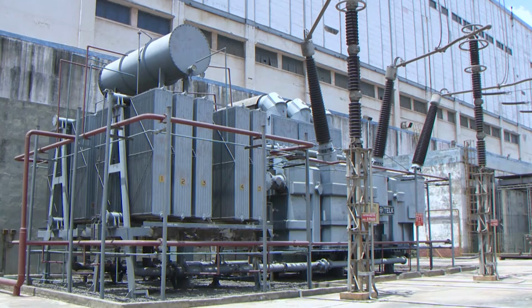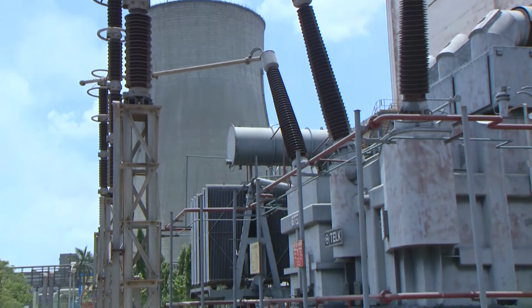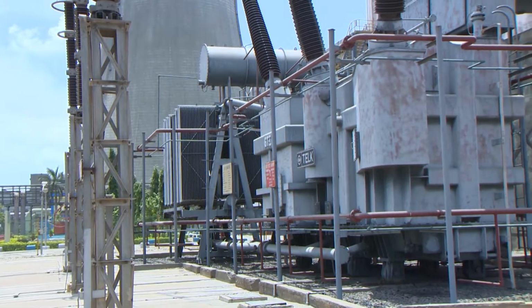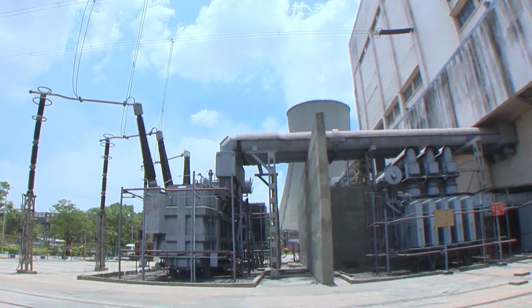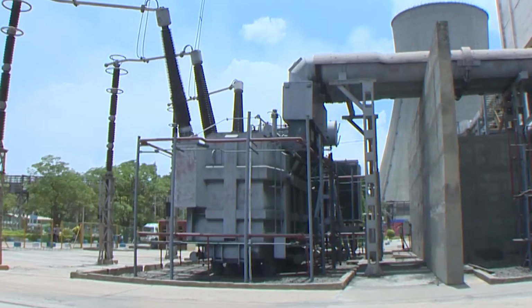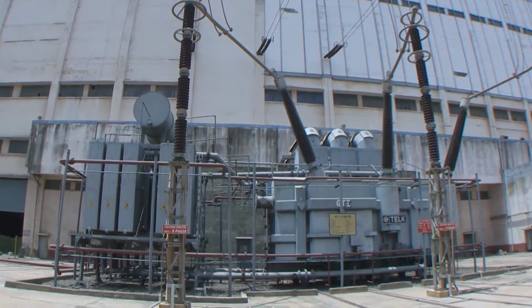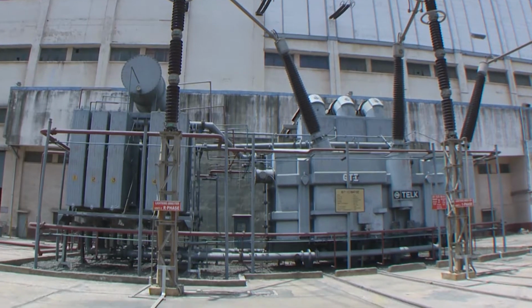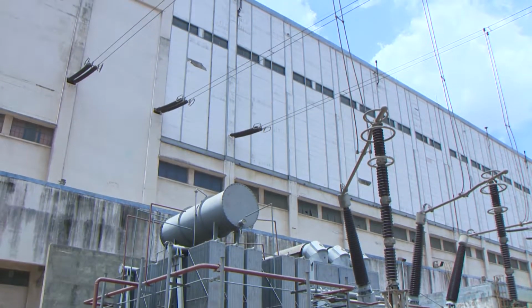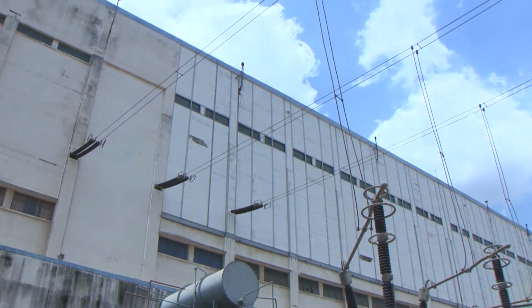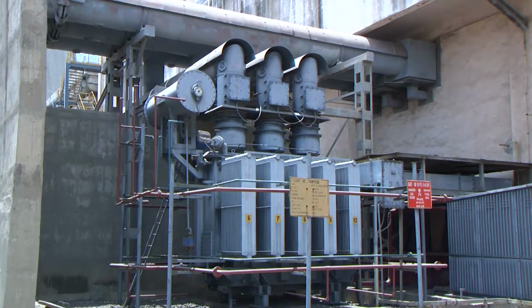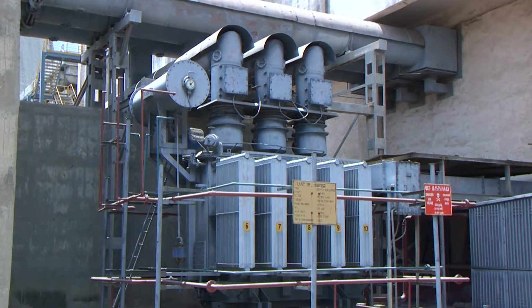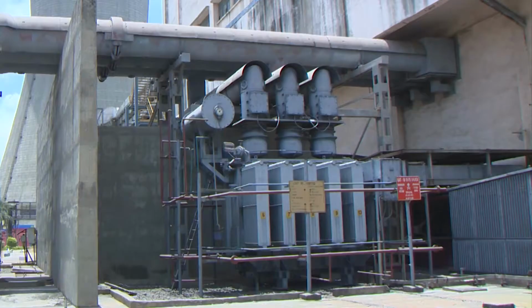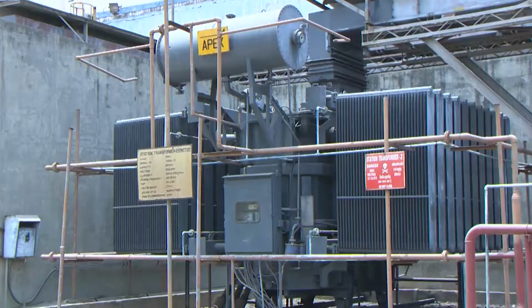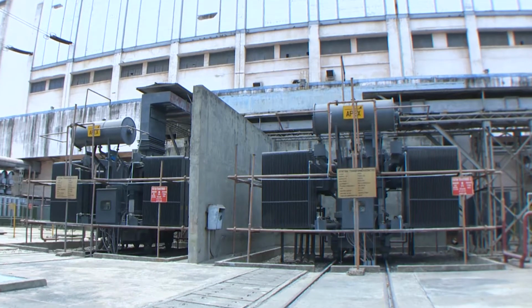Power transformers. Transformer is a device that transfers electric energy with changed value of voltage and current. It can be classified based on application. Generator transformer is the high-capacity transformers connected between generator and high-voltage bus to evacuate the power at high voltage. Unit auxiliary transformer is a transformer fed from a generating unit to feed the auxiliary buses or loads of the same unit at reduced voltage. Station transformer is a transformer fed from high voltage grid to feed the common loads of the station.